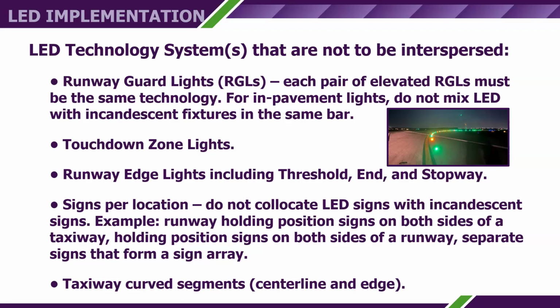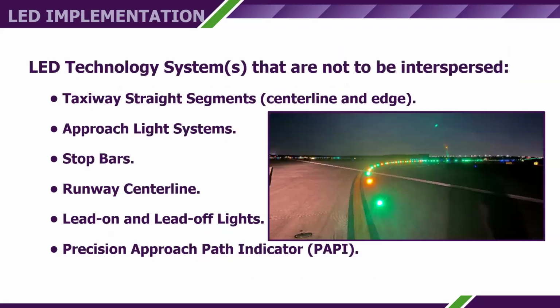Taxiway curve segments, centerline and edge: you cannot mix incandescent and LEDs in the middle of a curve, whether it's a centerline or an edge light circuit. And taxiway straight segments, you can't break it in the middle of the straight segment. You'd have to go to the end where it starts a curve. You have to have a consistent layout of all LEDs or a consistent layout of all incandescents. The entire airport on a taxiway does not need to be changed at the same time. You just need to have clear breakpoints between the technologies. And in my experience, it's best to coordinate that with your local ADO to make sure that they're in agreement with where you're planning to break the system or change the system from LED to incandescent or vice versa.